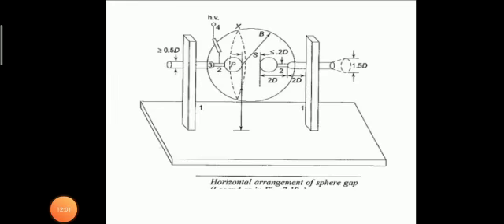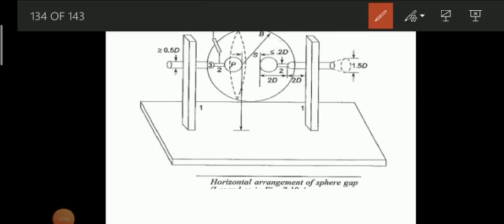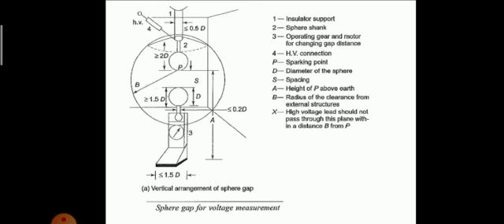Now same is this here. You can see here also, 4 is the HV terminal, 3 is the operating gear, 2 is the sphere shank. Four is the HV connection. P is the sparking point. X, the high voltage lead, should not be passing through this plane. B is the radius of clearance. S is the distance. D is the diameter of the sphere. Whatever I have mentioned here, these all hold good for horizontal or vertical arrangement of the gaps.